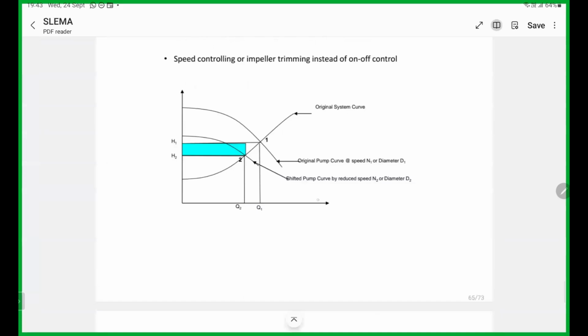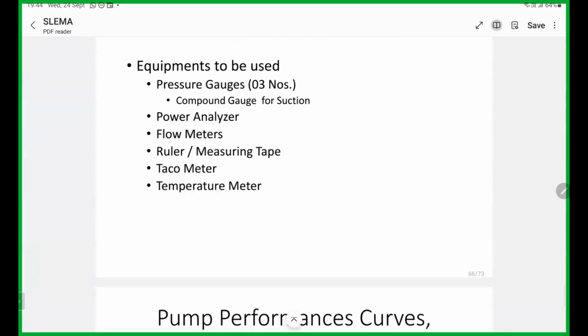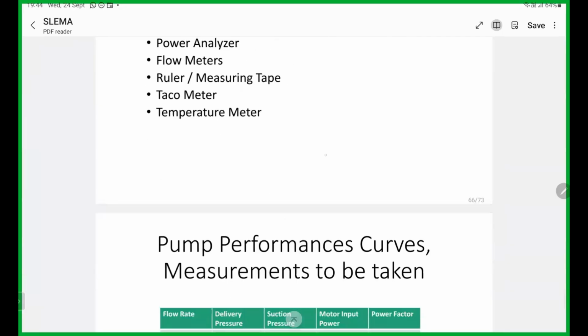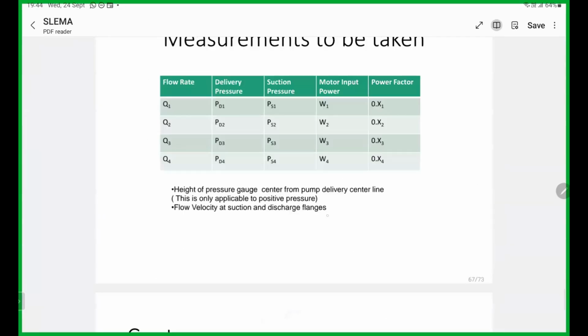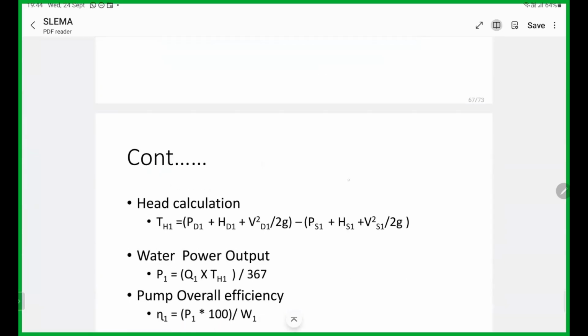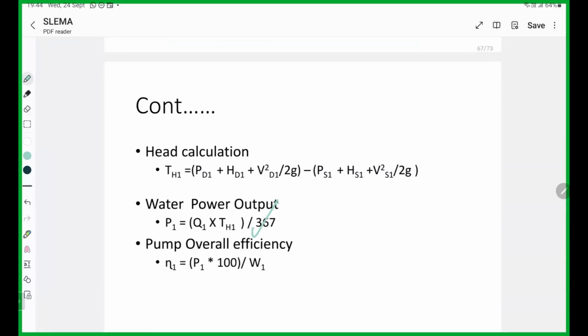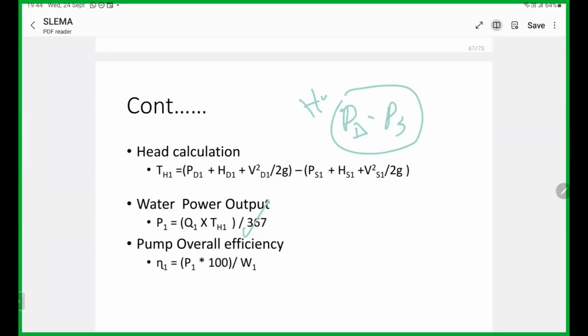For energy auditing you need equipment such as pressure gauges, a power analyzer and a flow meter. Then you have to take measurements, which is very important. Then the power calculation: I've already mentioned that pump head is delivery pressure minus suction pressure. Keep in mind that this is the pump head. Flow rate we can measure directly from the flow meter. Then, knowing the head, you can calculate the power from the power analyzer and then the overall efficiency. Keep in mind that we get the overall efficiency in an energy audit.